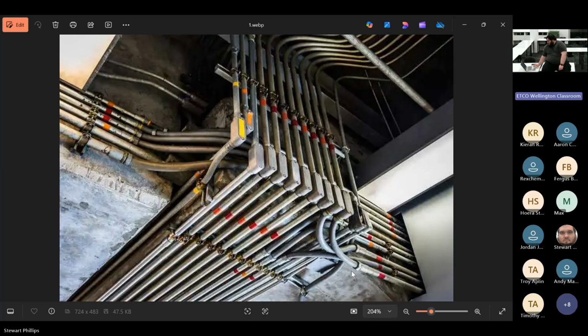Strength and mechanical stress. So steel conduit can take a lot more of an impact. So we can install it in a location where it's likely to be exposed to high velocity, basically high force impact. The one time I've done it in a residential situation was down a driveway. So we weren't allowed to dig up the driveway. Yep, it would be used in the mines. Yep.